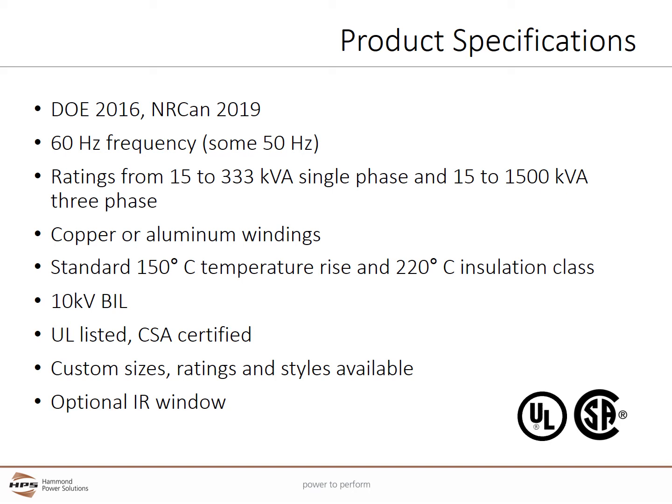Ratings are from 15 to 333 kVA single phase and 15 to 1500 kVA three phase. Copper or aluminum windings are available. Standard 150 degree C temperature rise and 220 degree C insulation class is used. Lower temperature rises are available. 10 kV BIL means the insulation system is designed to handle a 10,000 volt spike and not arc. All units are UL listed and CSA certified. Custom sizes, ratings, and styles are available upon request.